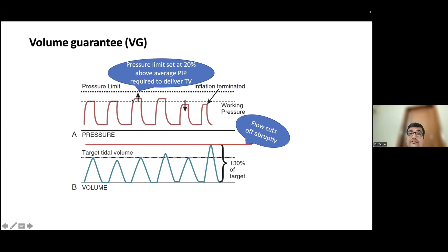And this pressure limit needs to be changed during the course of ventilation, so that this closed loop mechanism of ventilation remains intact. The second safety feature in volume guarantee ventilation is that if the delivered tidal volume exceeds 130% of the target tidal volume, which means the ET leak is more than 30 to 40%, and the ventilator is required to deliver a tidal volume that is 130% of the target tidal volume, then the flow will cut off abruptly, so that the working pressure will not increase. Okay, so these are the two safety mechanisms in volume guarantee ventilation. So it will not work when the leak is exceeding 30 to 40%, and the working pressure cannot increase beyond the pressure limit.